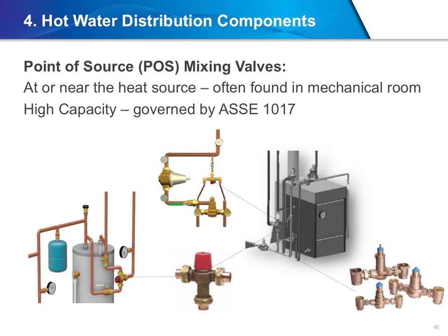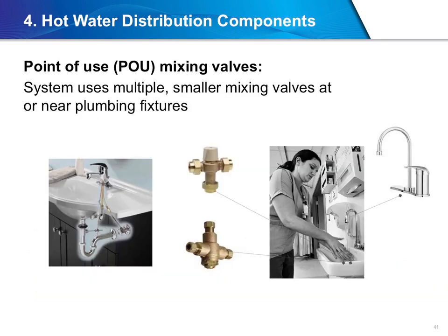There are two fundamental types of mixing valve systems: point of source and point of use. A point of source, or POS system, locates valves at or near the water heating source and typically has a higher capacity for controlled temperature water. A point of use, or POU system, uses multiple smaller mixing valves at or near plumbing fixtures, such as showers, lavatories, whirlpools, and emergency fixtures.